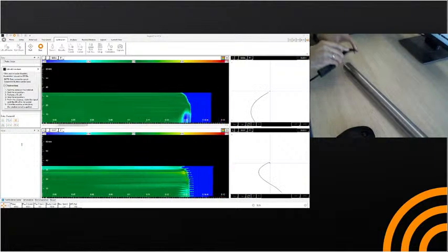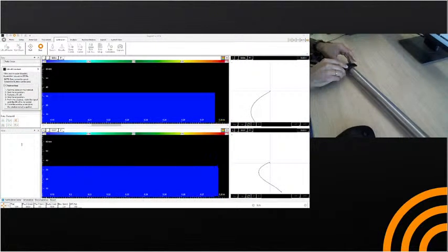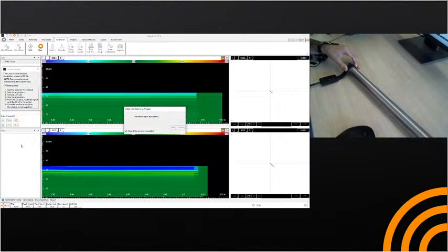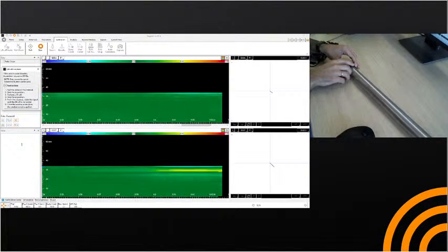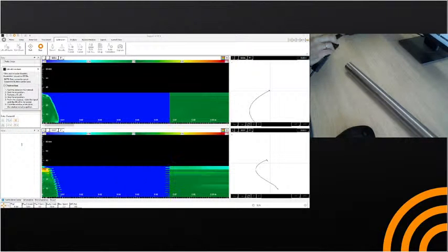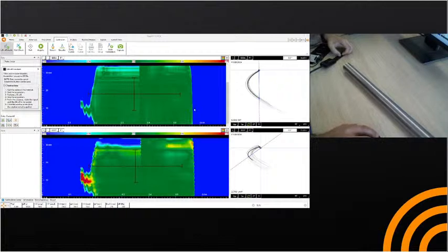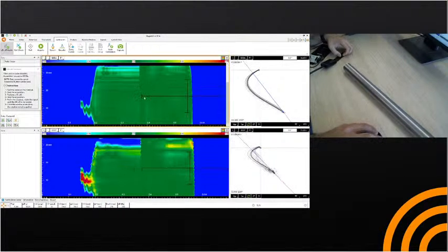So this is my first liftoff. You can actually do 2, 3 liftoffs just to make sure you have it right. I balance again, and perform the liftoff. So as you can see here, I'm placing my cursor on the liftoff signal.